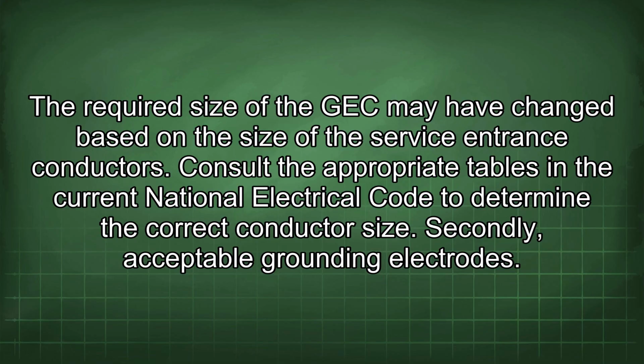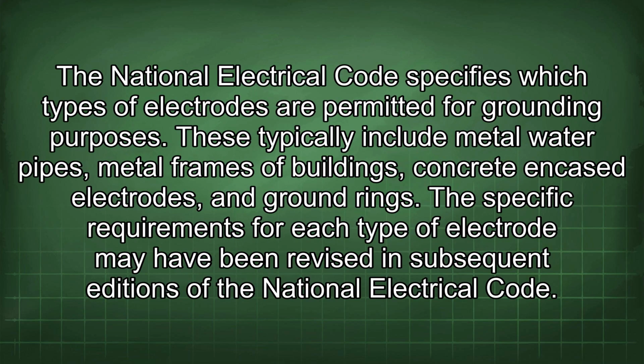Secondly, acceptable grounding electrodes. The National Electrical Code specifies which types of electrodes are permitted for grounding purposes. These typically include metal water pipes, metal frames of buildings, concrete encased electrodes, and ground rings. The specific requirements for each type of electrode may have been revised in subsequent editions of the National Electrical Code.